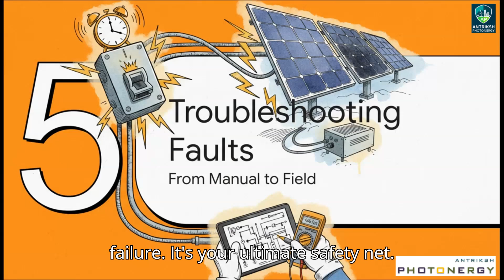Okay, this is where the rubber meets the road. An alarm is blaring, a breaker's tripped, and everyone's looking at you to figure out what on earth just happened. So, let's walk through how you should approach this. Let's take a classic case. You're getting frequent overvoltage trips. Now, the single most important thing here is to be methodical. Whatever you do, don't just walk up and reset the relay, please.